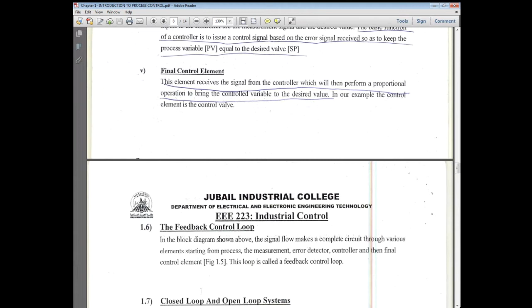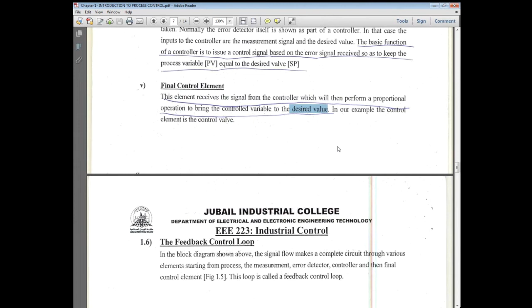Okay, now see here, Shabab. Feedback final control element. The element receives the signal from the controller, which will then perform a proportional operation to bring the controlled variable to the desired value. So PV will become near to the set point. What is desired value, Shabab? Desired value is set point. Shabab with me? Yes, teacher. And what is the controlled variable? That we want to control, PV. So the final control element can be a valve, control valve, solenoid valve, a pump, a lot of other equipment that helps the controller to bring the controlled variable equal to or near the desired value, that is the set point.